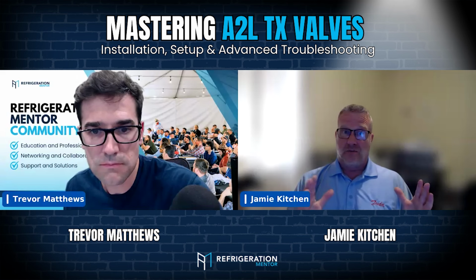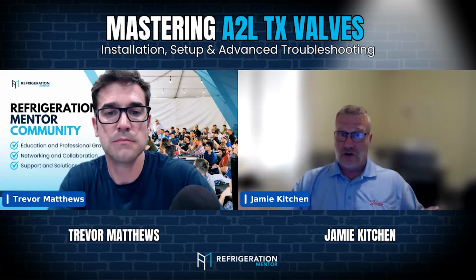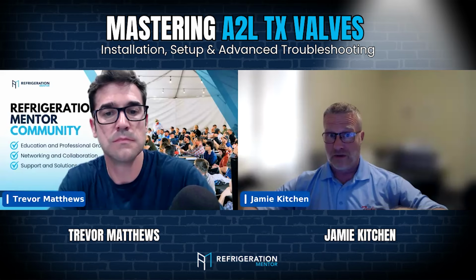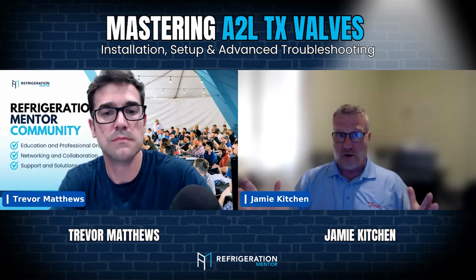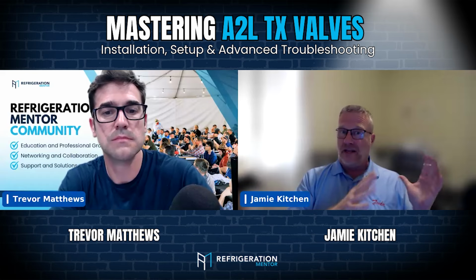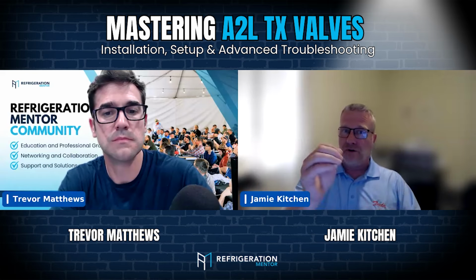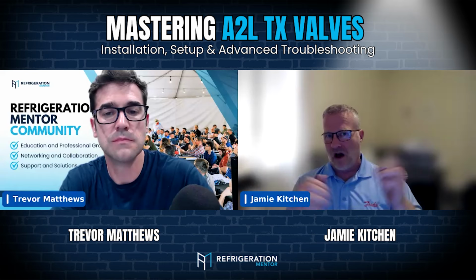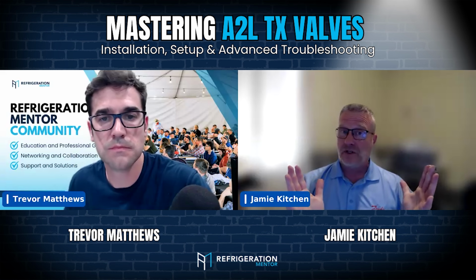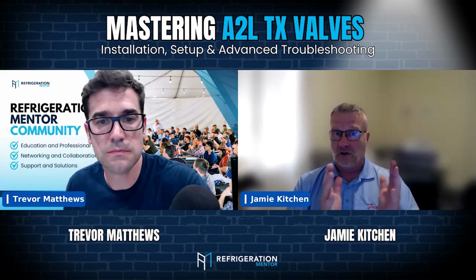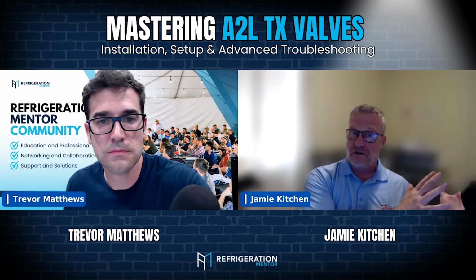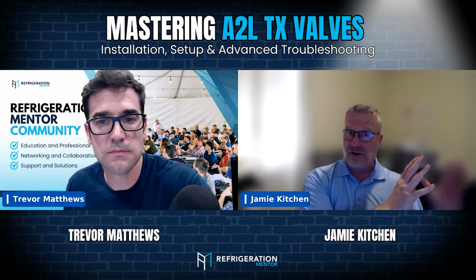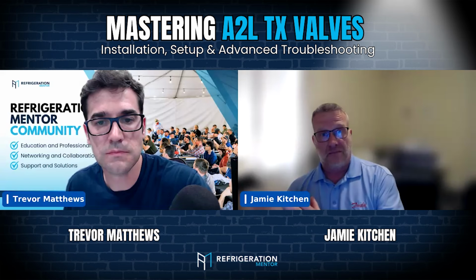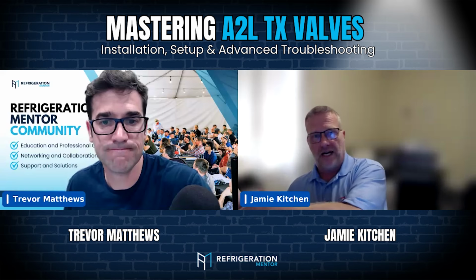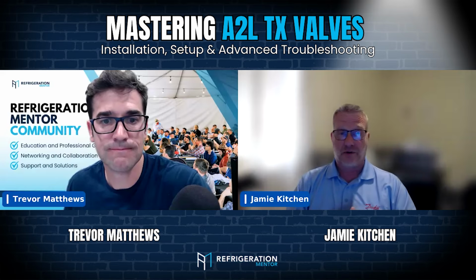Whereas some of these other blends almost act like you just took a bunch of different refrigerants and poured them in. I don't want to use the word auto cascade, but if you know what that means, you'll understand where I'm going. The different refrigerants boil off at different rates, and that's what gives you your glide. When you first go into your evaporator, a specific refrigerant is going to boil off faster than the remaining ones. Then the next one boils off, and the next one, and this affects your temperature and pressure.